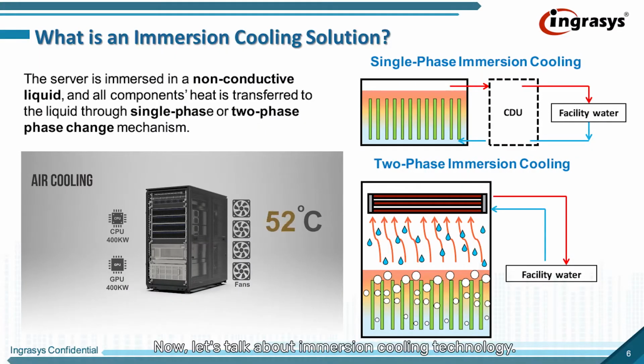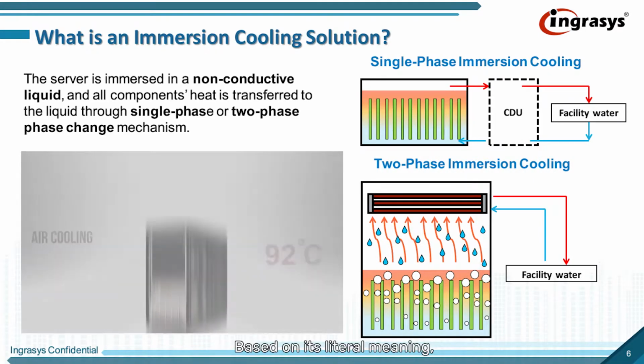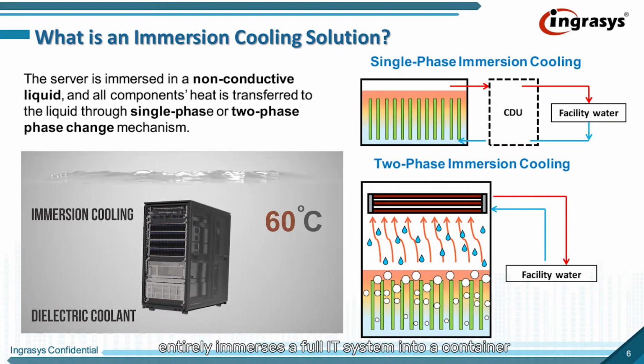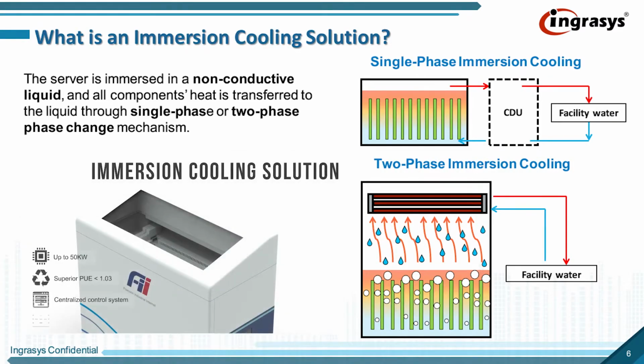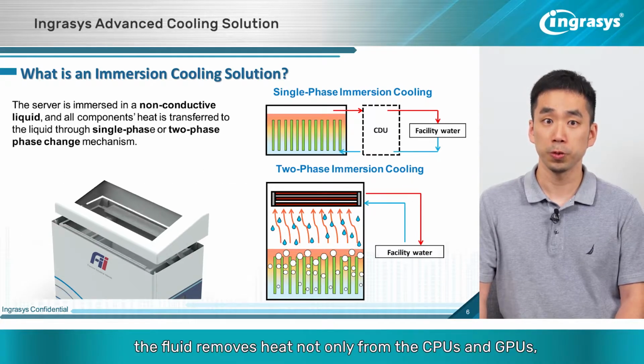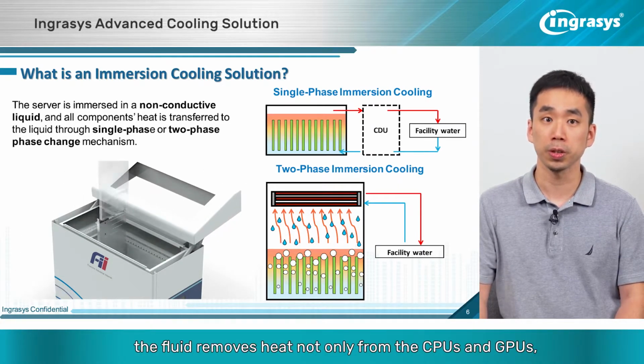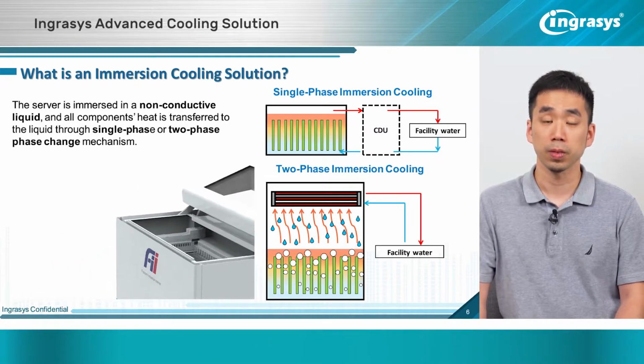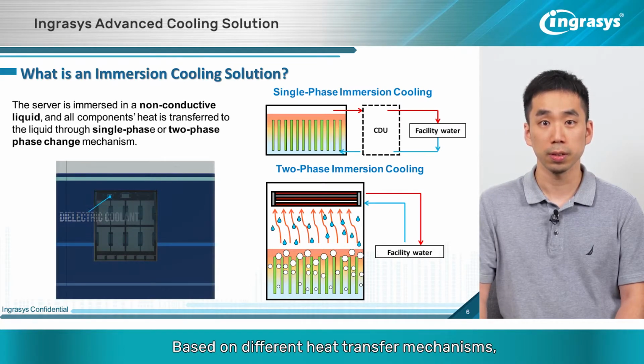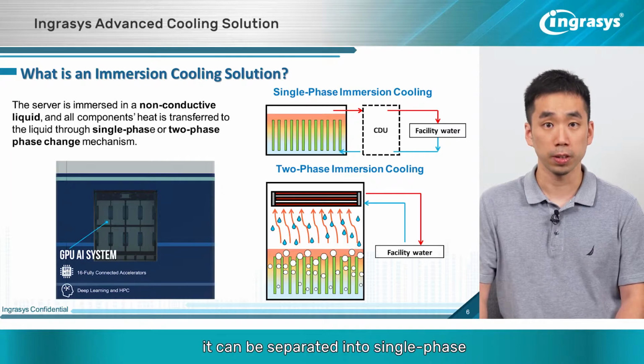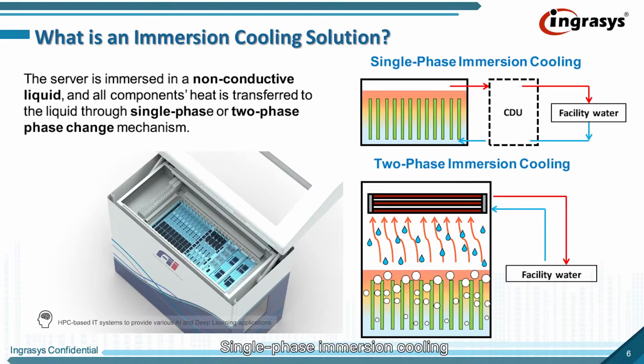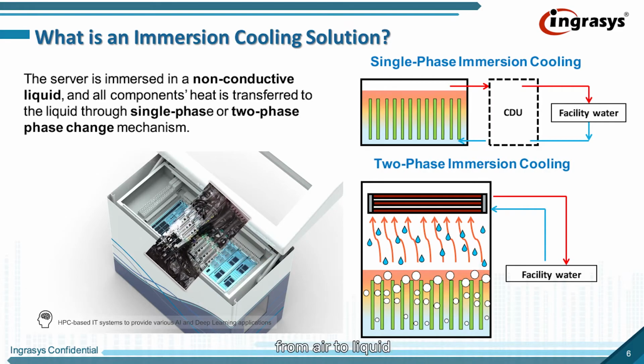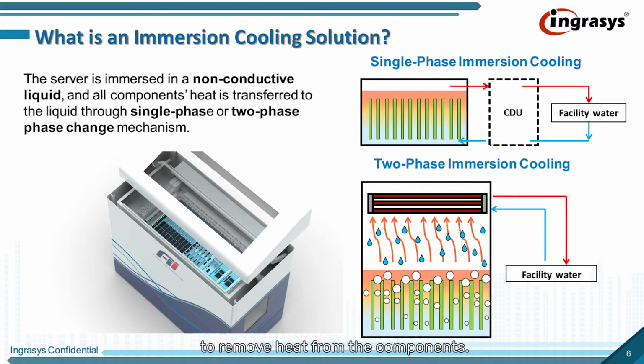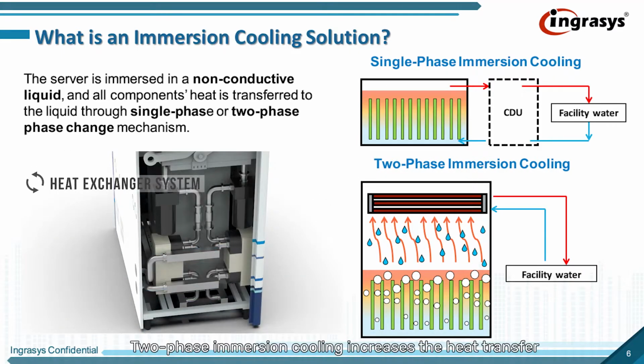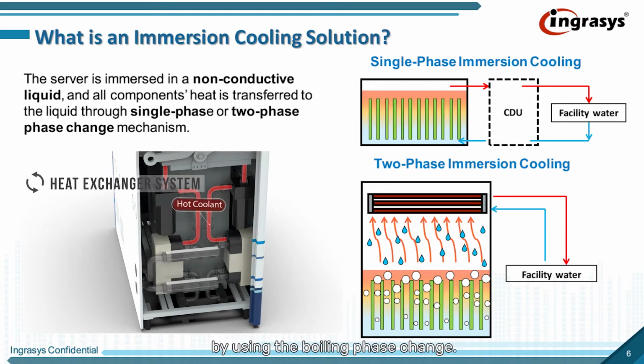Now, let's talk about immersion cooling technology. Based on its literal meaning, this cooling technology entirely immerses a full IT system into a container filled with an electrical non-conductive fluid. In this environment, the fluid removes heat not only from the CPUs and GPUs, but from all components in the system. Based on different heat transfer mechanisms, it can be separated into single-phase and two-phase immersion cooling. Single-phase immersion cooling changes the heat transfer media from air to liquid and uses forced convection to remove heat from the components. Two-phase immersion cooling increases the heat transfer by using the boiling phase change.